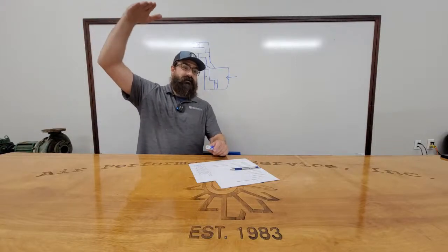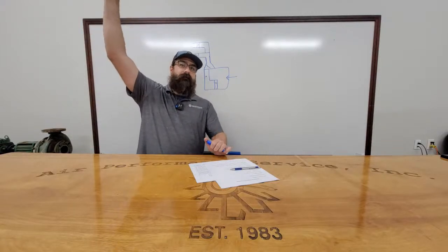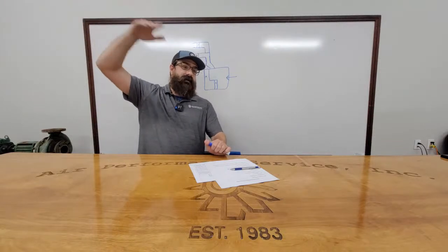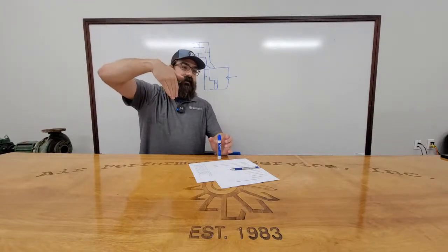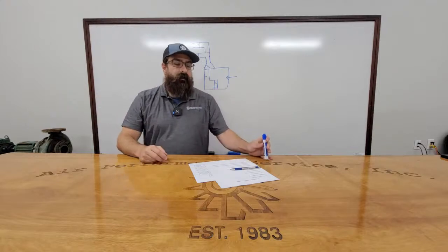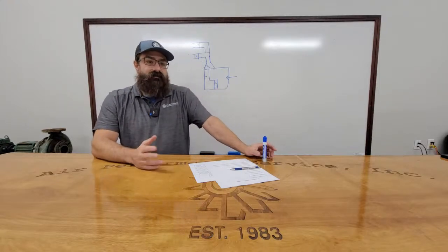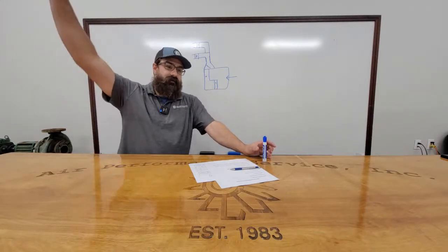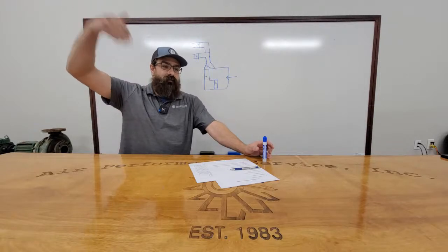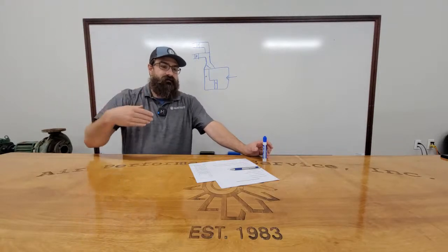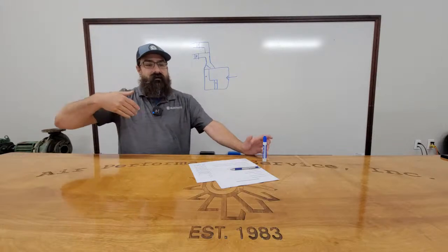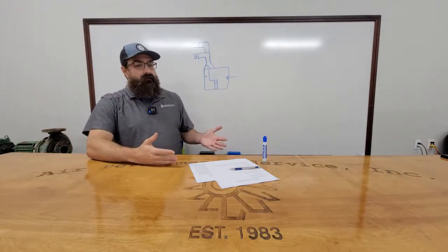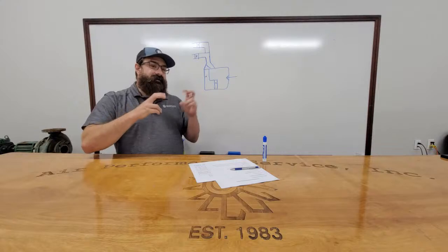That VAV box, it's an ERV, so it's using exhaust air to temper the air coming in, with some desiccant wheels and all that. Yeah, for like free cooling, basically energy conservation. That way you're not just dumping your cold air out and bringing in hot air. You're recovering some of the energy through the wheel, but that is pumping in and then being fed into the return of that unit, right? Mm-hmm. So it is cooling to some extent.